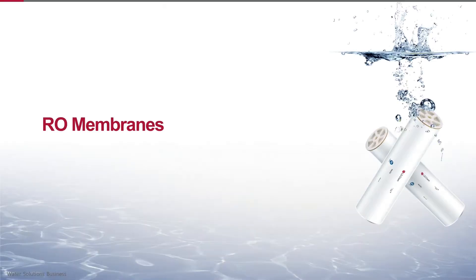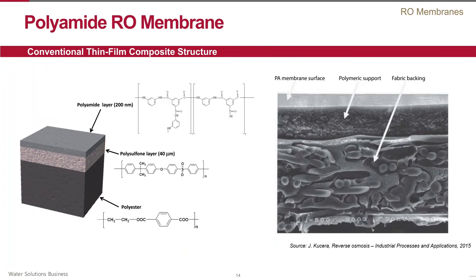As you understand, the most important component of the reverse osmosis process is the membrane. Today, the most widely used type of RO membrane is a polyamide thin film composite. It consists of three layers: a semipermeable thin layer that is less than 0.2 micron — 200 nanometers or less — made of aromatic polyamide, which is supported by two layers.